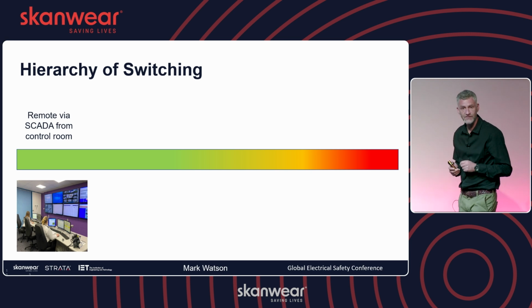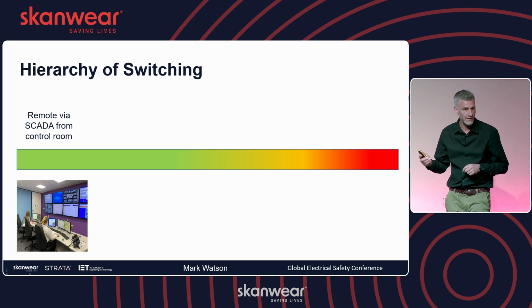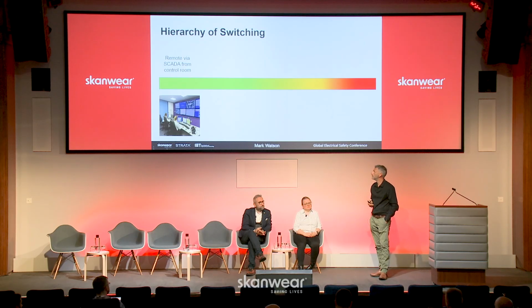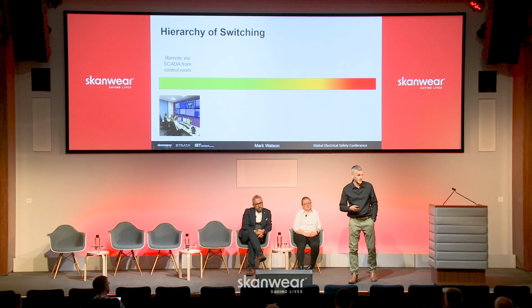Great if you've got a fancy control room and the ability to do it. On our new installations we can do remote operations on everything - circuit breakers, disconnectors, earth switches - and our process is to do them all remotely, keeping everybody out of harm's way. In theory, all the AP does is put a padlock on at the end.